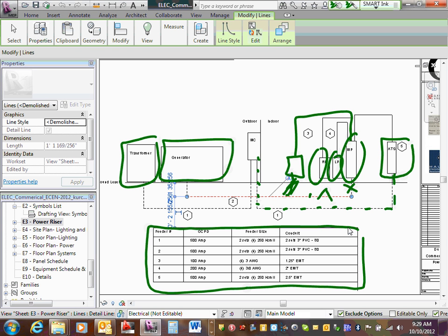As long as we have Joe here, do you guys have any question about the load calculation, about the circuiting? We were just talking about circuiting today. Branch circuits, how many lights you throw in one 20 amp branch circuit, how many receptacles you can throw in 20 amp circuits. Do you have a rule of thumb, Joe, for these? I usually use that little Xcel Energy cheat sheet that says a 3-lamp fluorescent fixture with an electronic ballast is 85 watts and a 2-lamp is 58 watts, and so when I'm circuiting lighting, that's what I usually use.